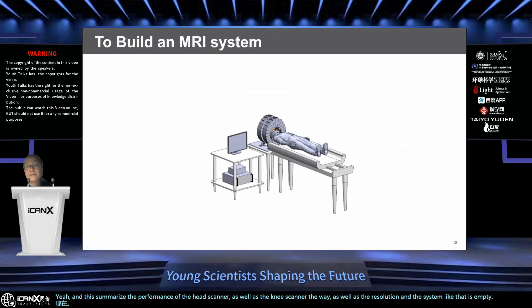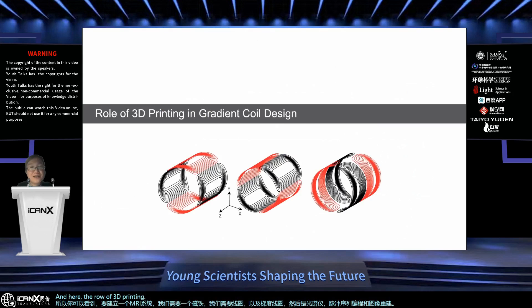To build an MRI system, we need a magnet, an RF coil, a gradient coil, and then a spectrometer, pulse sequence programming, and image reconstruction. And here, the role of 3D printing in gradient coil design is such. We know that the gradient coil is used for encoding and for readout. The photo on the right gives us a more direct illustration of how important the gradient is. Traditionally, a gradient coil is made in a very labor intensive way. On the right-hand side is a 3D printed one that we made in the lab for a lab magnet.